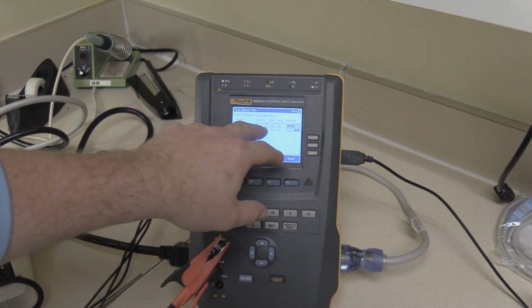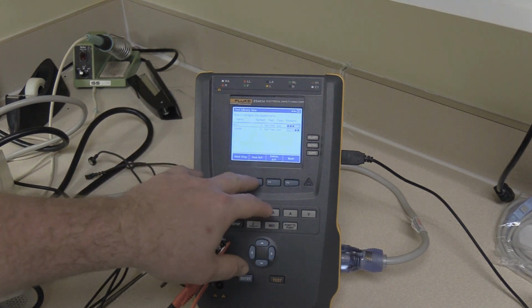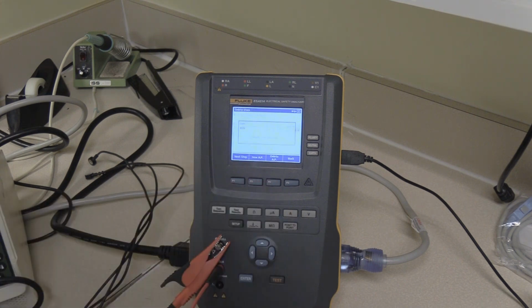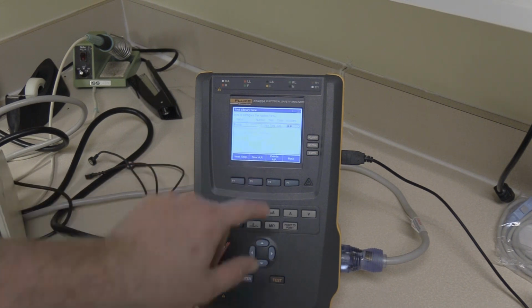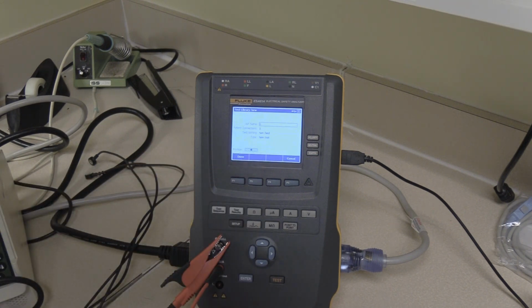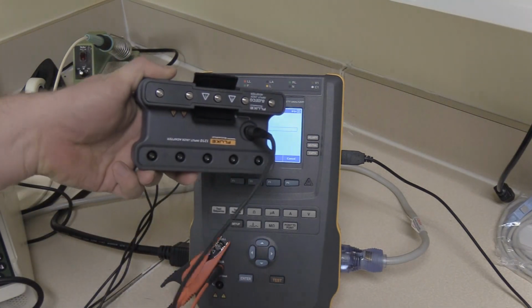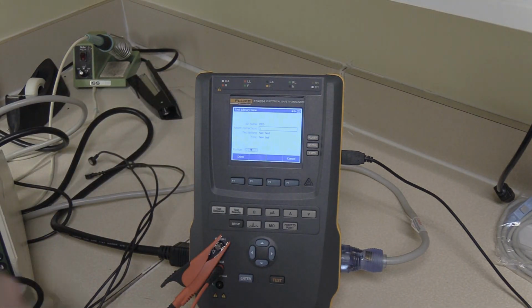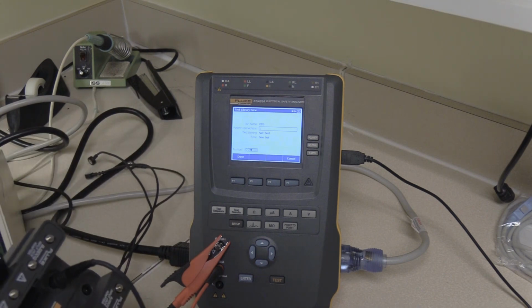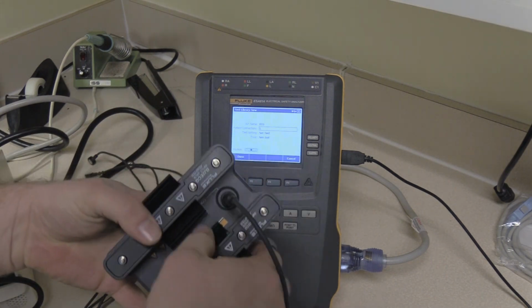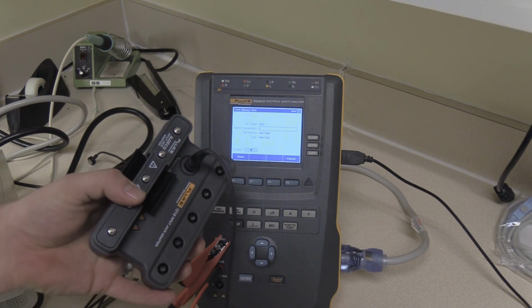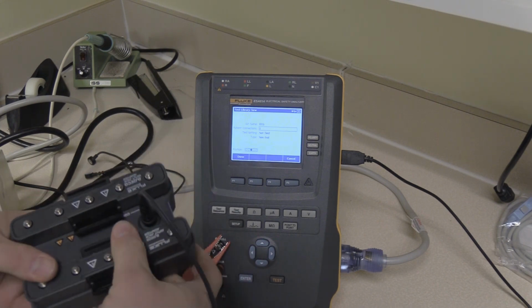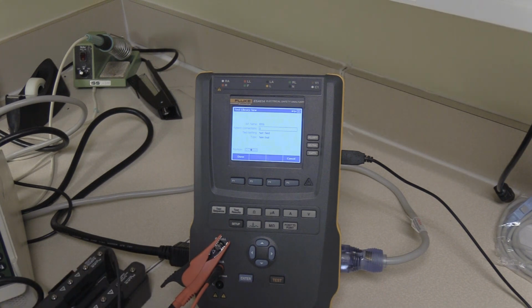So first thing we're going to do is delete the ECG, and are we sure? Yes. Now we're going to create a new applied parts test and title it ECG. Now, since we're going to use the 1 to 10 adapter, we're only going to need 1 patient connector. See here, that's where they all connect in. There's only 1 output, so we're going to use 1 connector. We'll put the other ECG snap on while we're here. That gives you the ability to put 5 on one side and 5 on the other. If you need, the banana pins are right there as well.